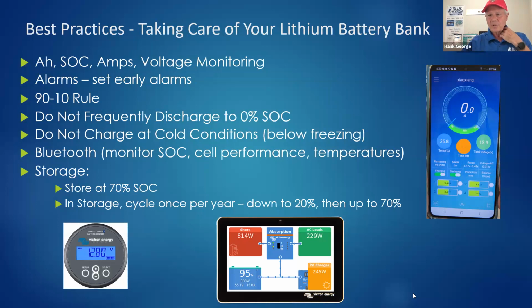That gets all the equipment recalibrated. You fully exercise all the lithium that's in solution in your battery, you're getting it all used. So periodically you can go above 90% and periodically you can go below 10%, you just don't want to stay in those zones. That's sort of the frequently discharged issue.